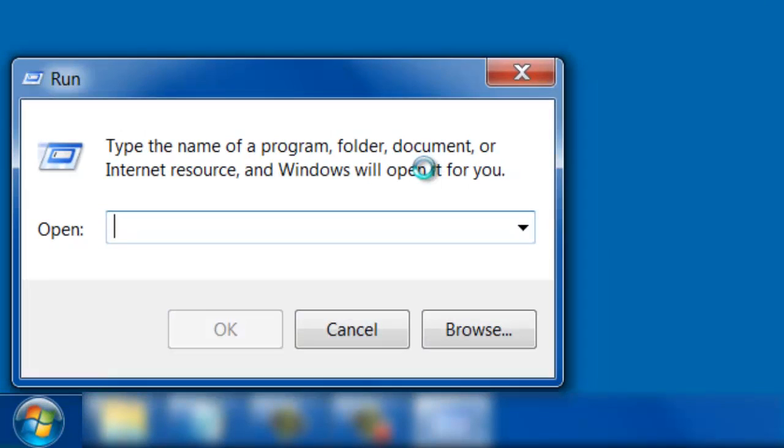To be able to use the service adapter within the service software LoopMaster, we first need to identify the associated COM port number. Please open the Device Manager by selecting Run from the Start menu and entering devmgmt.msc.